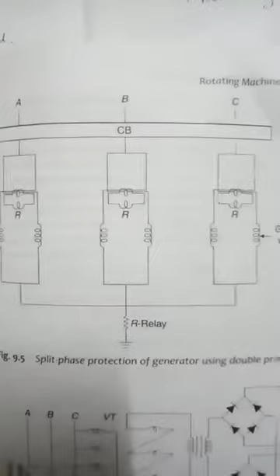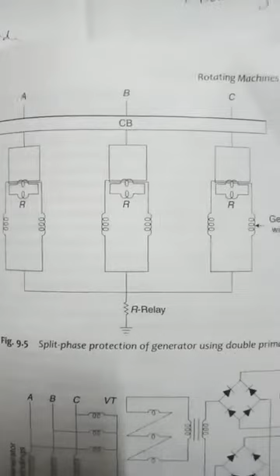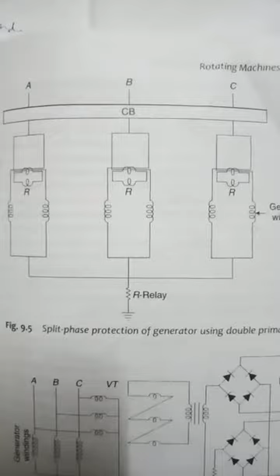A faster and more sensitive split phase protection is shown here in the figure, which can be employed. In this scheme, a single CT having double primary is used. No bias is necessary because a common CT is employed, so errors due to CT differences do not occur.